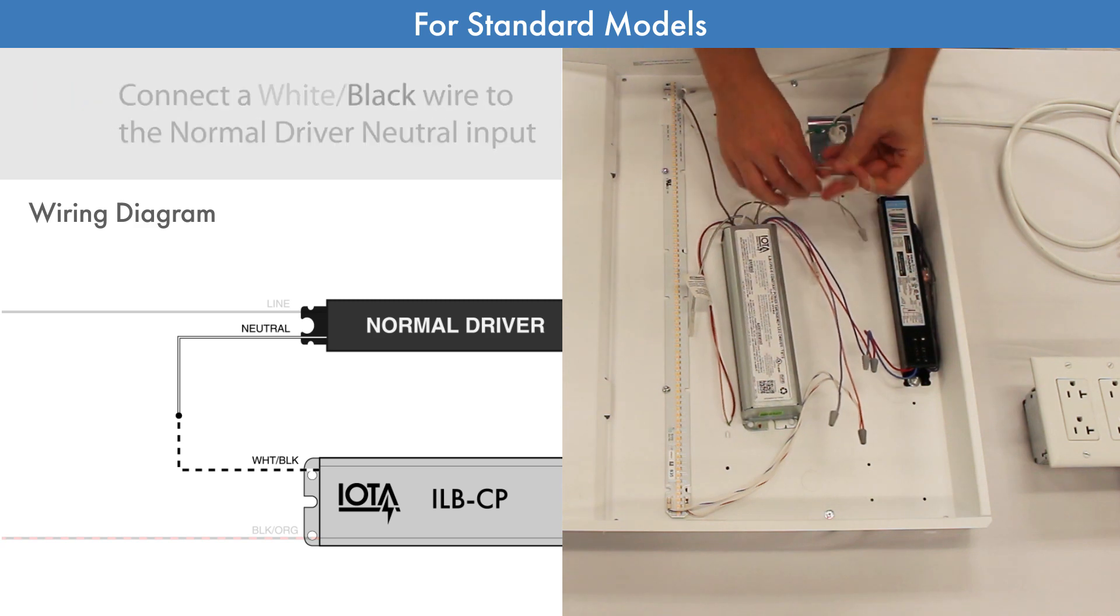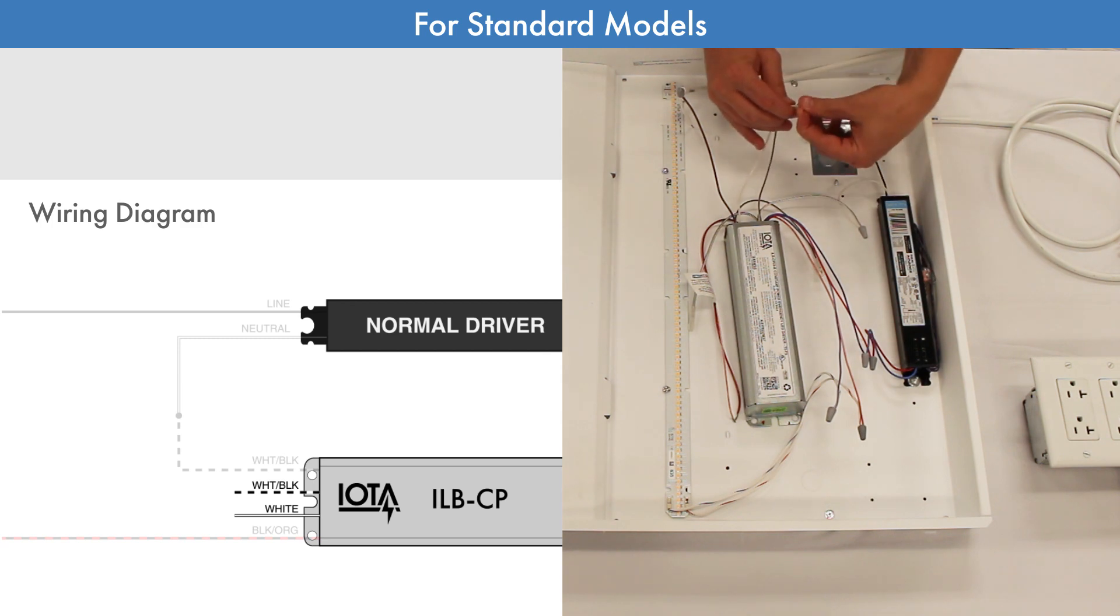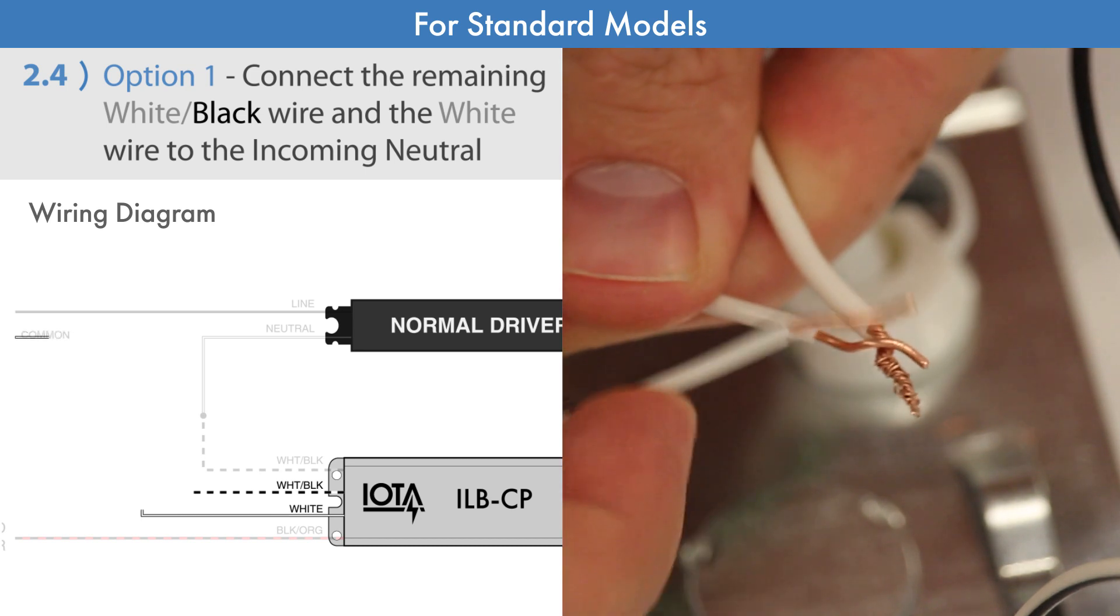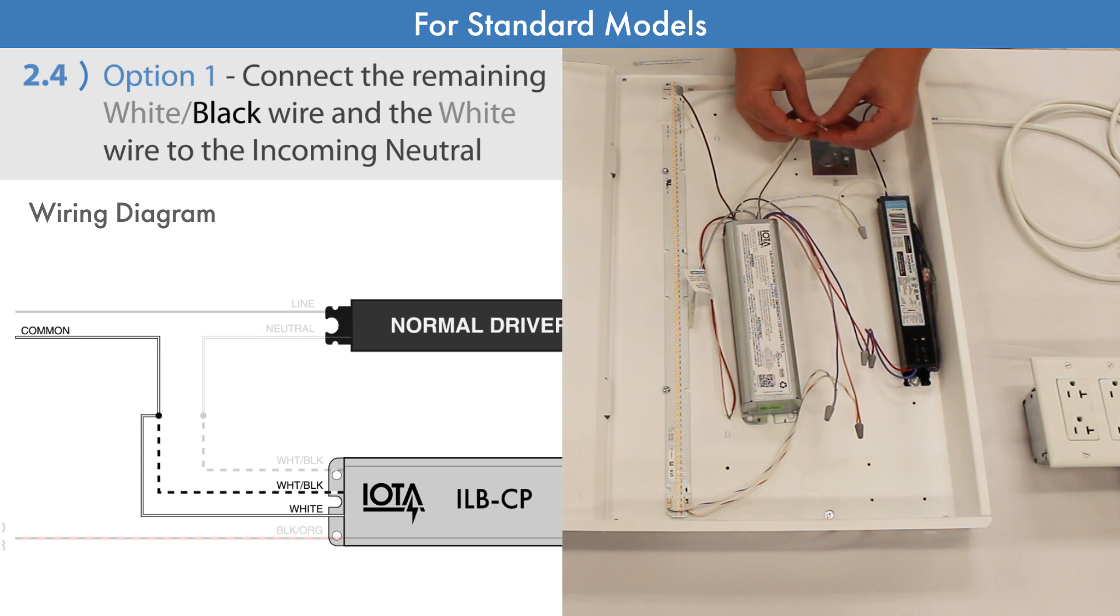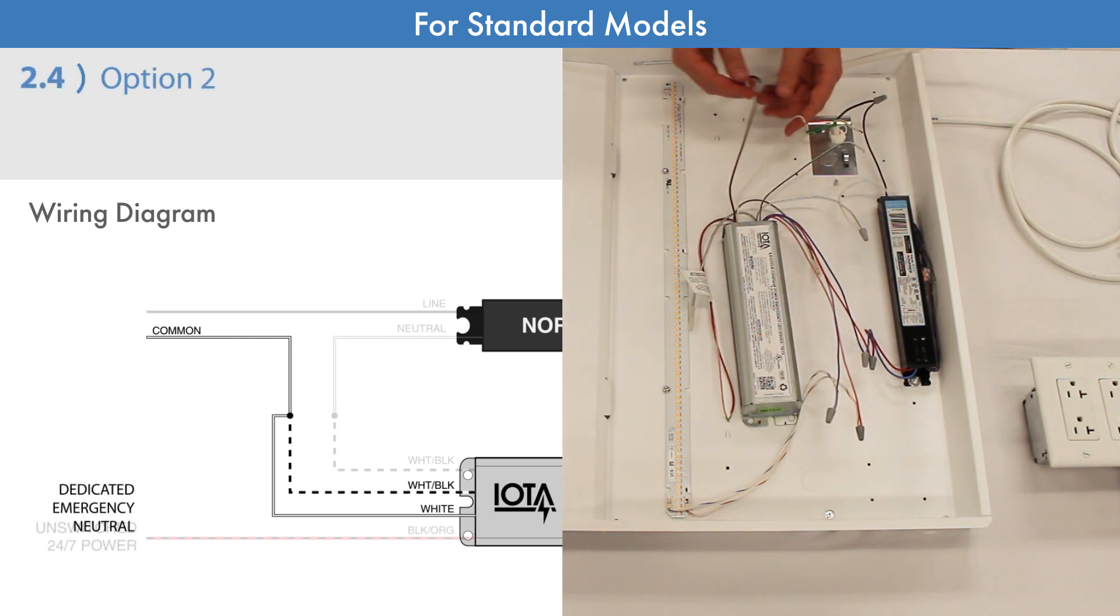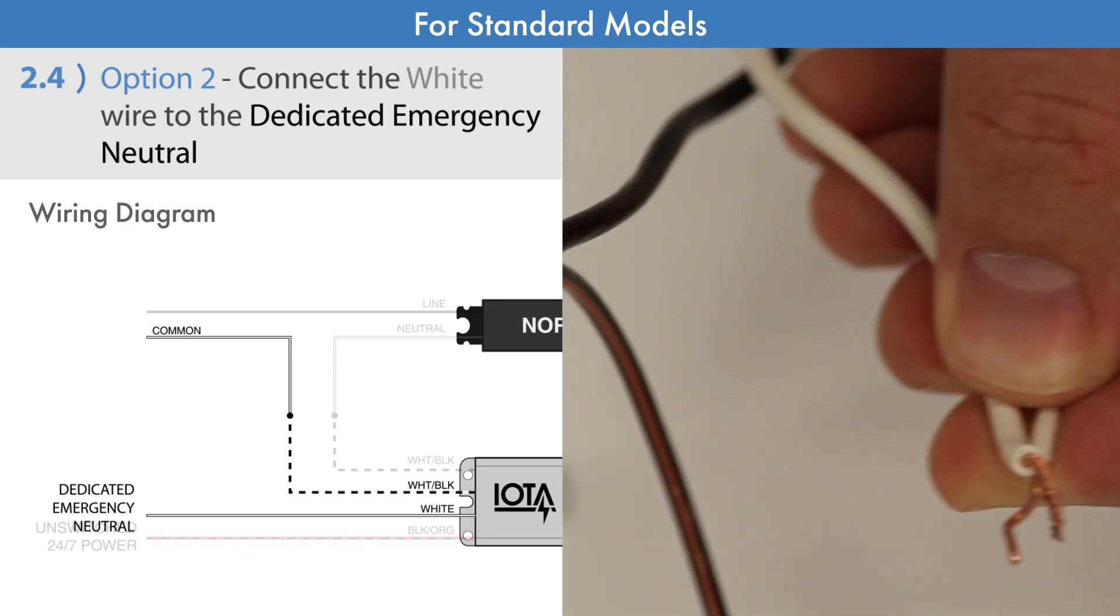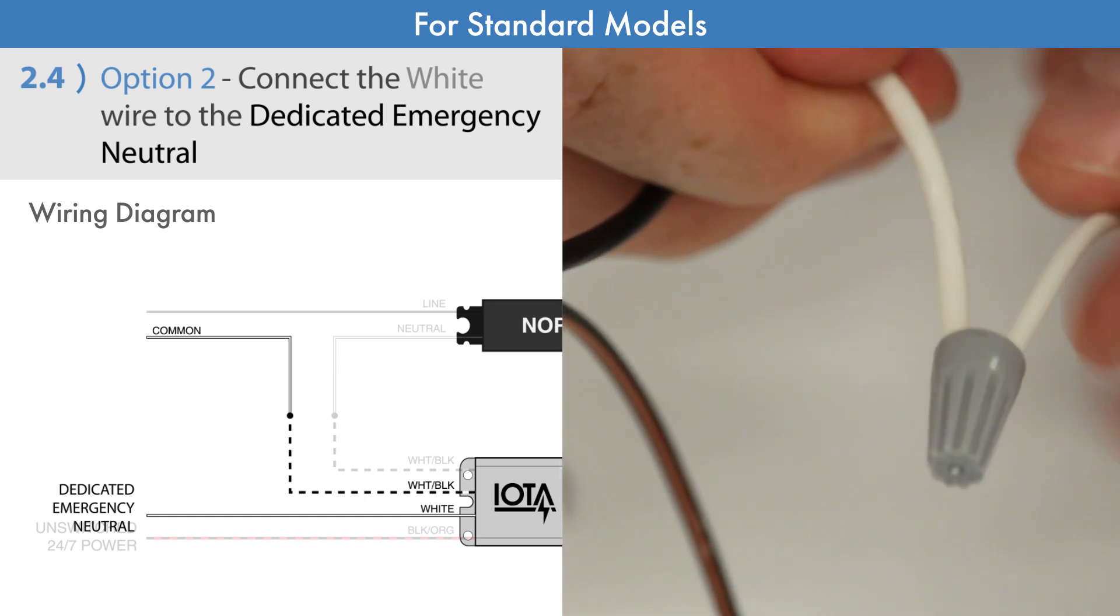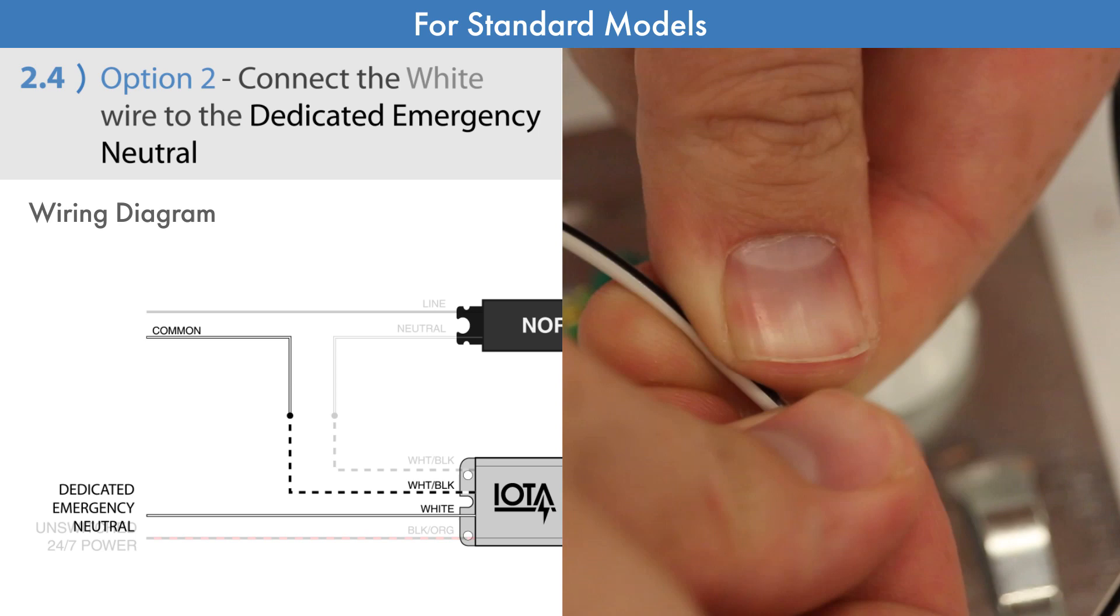Then we will connect the remaining white-black wire and the white wire. Depending on the design of your system, you have two choices for these wires. Typically, you will tie both of these wires together with the incoming neutral wire. However, if your system involves an electrical panel that is dedicated to emergency operation, the white wire may be connected to the dedicated emergency neutral instead. In this example, we have a dedicated emergency neutral, so we will connect the white wire to it, and connect the remaining white-black wire to the LED fixture's incoming neutral.